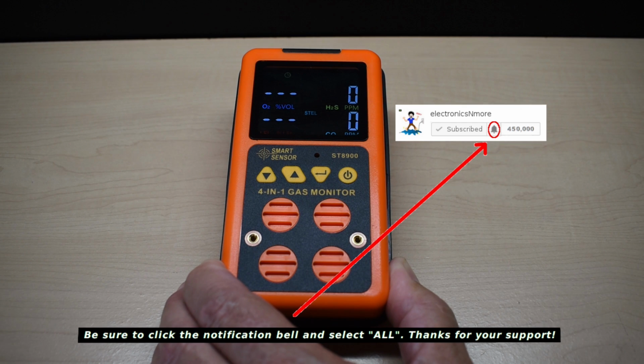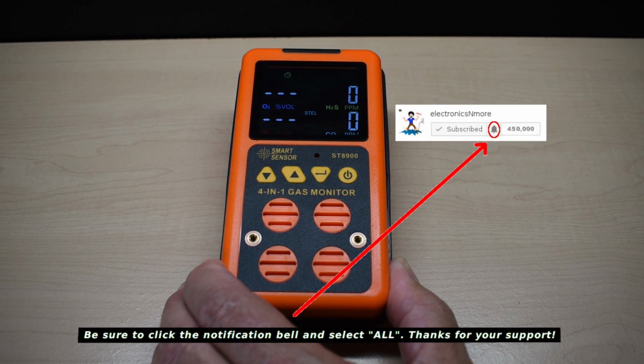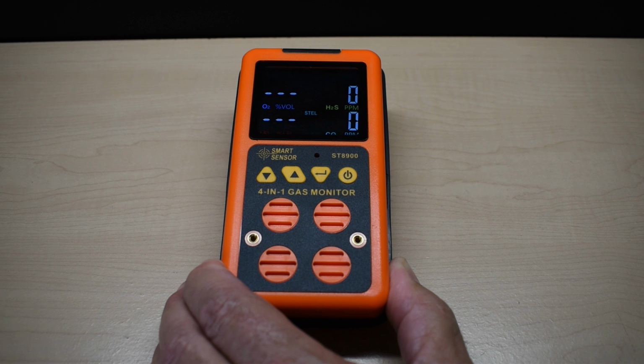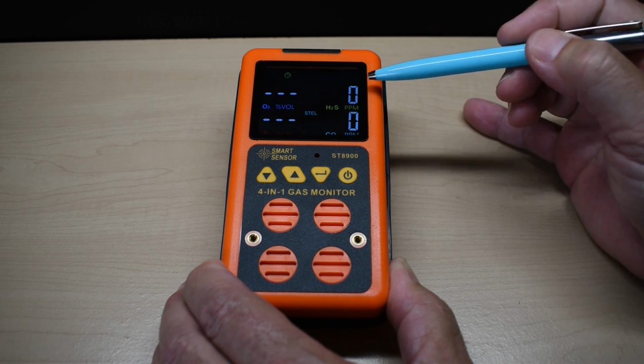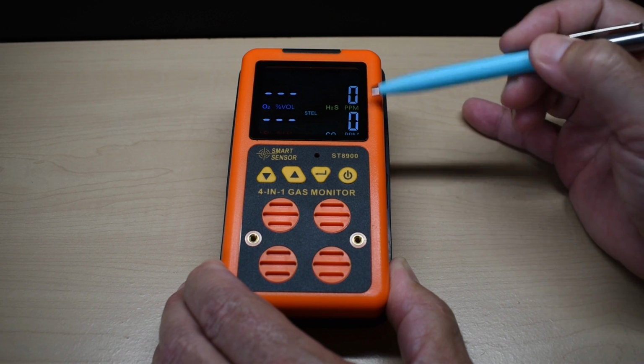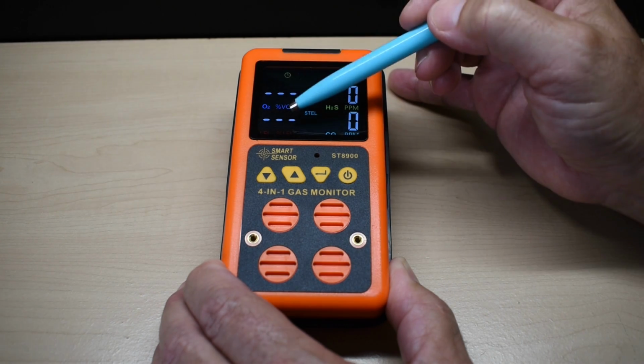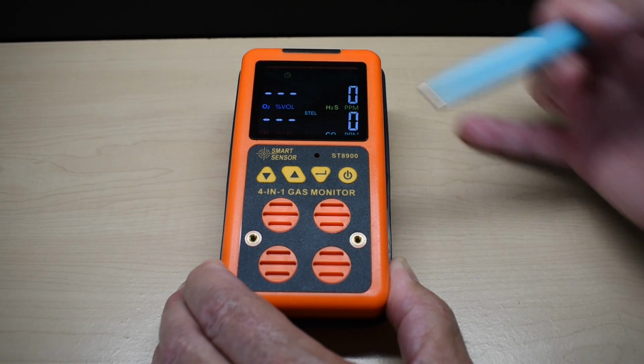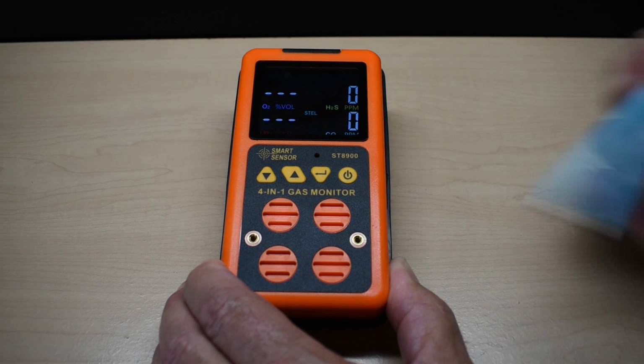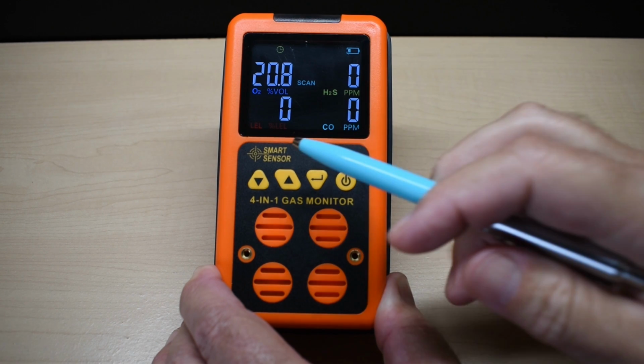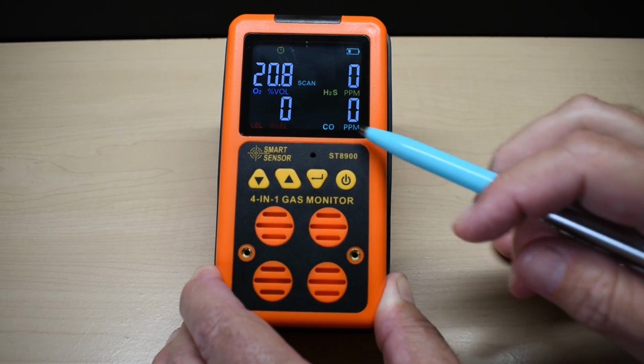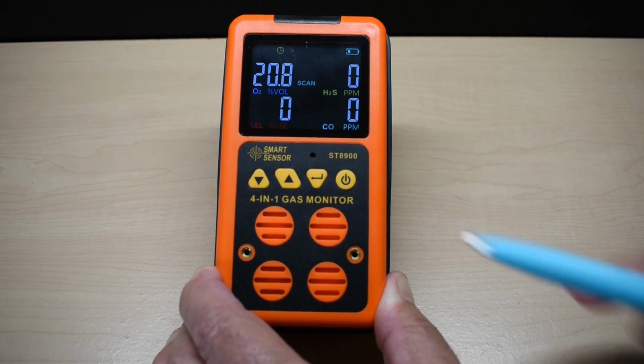So if I push this right here, now it says STEL. That's short-term exposure limit, and that's over 15 minutes. It's going to average everything right here over the 15-minute period and place it in the same area. Just like the other setting, when you power the unit off, it's going to reset. Right here, in case you couldn't see it before, it says LEL, and you can see down here CO PPM.